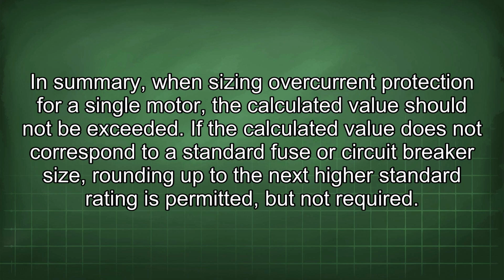In summary, when sizing overcurrent protection for a single motor, the calculated value should not be exceeded. If the calculated value does not correspond to a standard fuse or circuit breaker size, rounding up to the next higher standard rating is permitted, but not required.